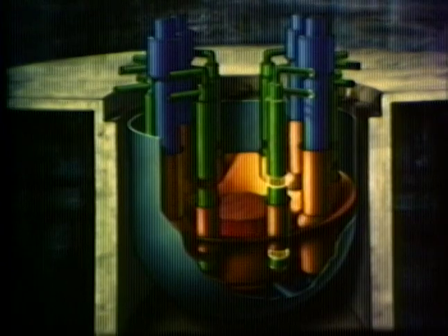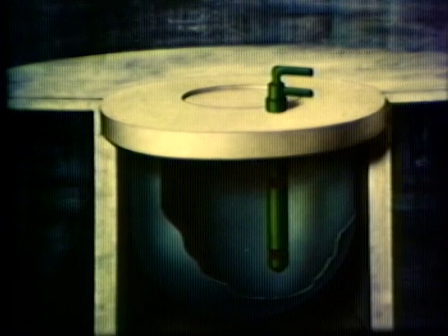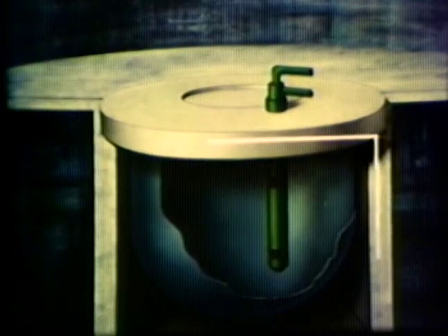Here is one of the 8 heat exchangers, 18 meters high and weighing 80 tons when empty. Through the top of the upper slab from which the heat exchanger is hung, secondary sodium enters and exits. Heat transfer takes place in the body of the component, inside the tube bundle consisting of 5,400 tubes, each 6.5 meters long, welded between two circular plates.